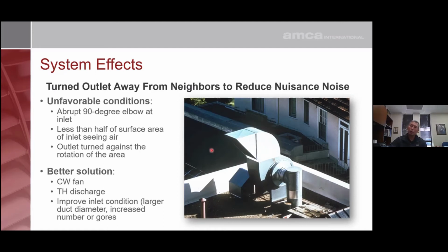Inlet side, we have an abrupt 90-degree elbow that creates a lot of turbulence of the air going into the fan. And if we look at the inlet size, this large disc or circle is the actual inlet size of the fan. They had to put an orifice plate here in order to contract this duct and adapt this ductwork to the inlet side of the fan. When this fan was tested afterwards, it was found to only be performing about 60% of its rated capacity, way underperforming.